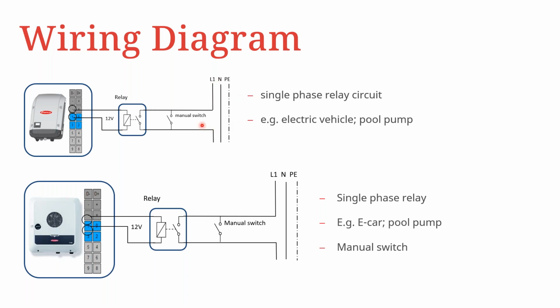What you can see here is also an inclusion of a manual switch, which would allow you to bypass the relay, so that if you do require this particular load to get into operation at any moment, you have this possibility using this manual bypass switch. For the Gen 24, it is a very similar schematic, very similar to the connection of the Data Manager with the Snap inverter.